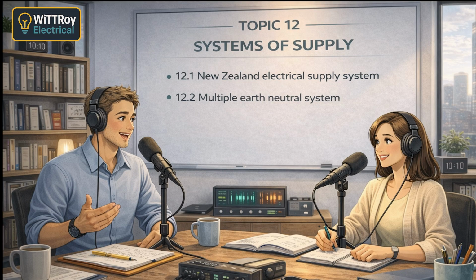Most houses are single phase, right? Most domestic installations are single-phase, yes. Some larger houses or workshops may have three-phase. And New Zealand uses a four-wire system. Yes, a three-phase four-wire system. That means 3 active phases and 1 neutral. So a three-phase customer gets all 3 phases and the neutral. Exactly. That gives them 400 volts between phases and 230 volts from any phase to neutral.